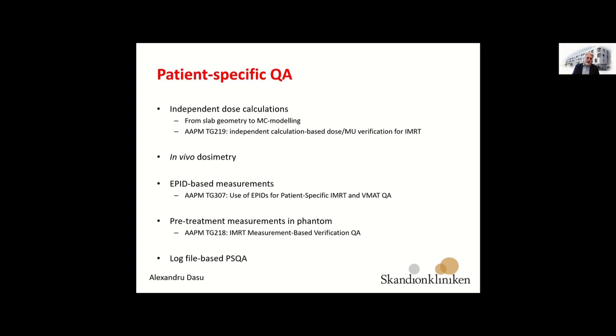And more importantly, log file-based patient-specific QA has found a use, especially in proton therapy. That is because modern machines log, with very high frequency, millisecond or better, all the parameters for their relevant settings during the treatment. And you could check there, of course, after the delivery of the radiation, whether the machine could deliver all the important parameters of the treatment. For example, the right energy, or the positioning, at least in proton therapy, the position of a spot of protons in spot scanned therapy. And you could check those parameters against those recommended from the treatment planning system. And from that, you could assess the accuracy of the machine in delivering the dose distribution.